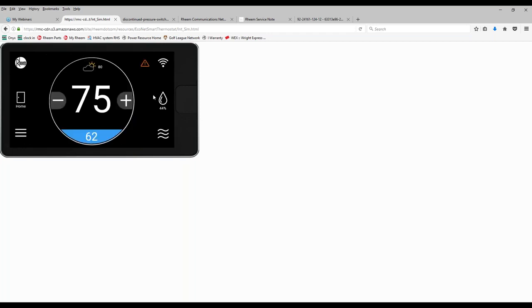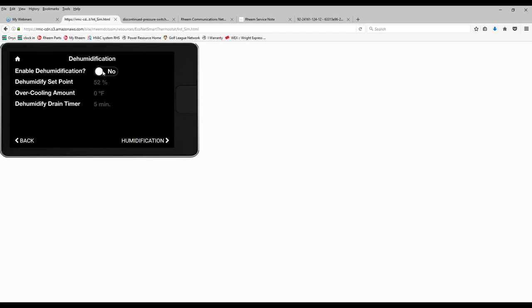I clicked on the humidity droplet here. At that point, you can enable dehumidification or not enable it. It comes factory set as no. So I clicked on humidification down here, enable it, and your humidity set point. When you want to humidify, you can do it during heat, cool, or heat and fan. You have a couple different options there on when you want to actually do humidification.